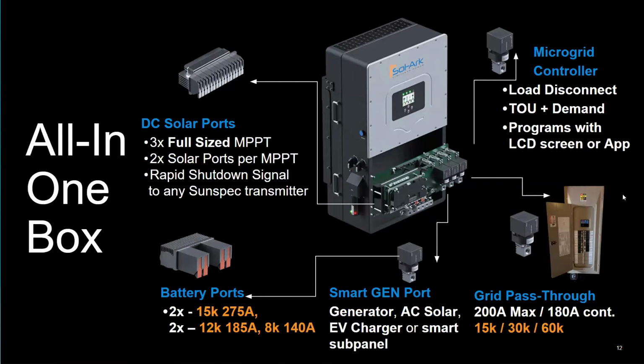Now, beyond that, there are a couple of strategies you can utilize. Instead of doing a 200 amp breaker, you could do a manual bypass, although you would still have to figure out overcurrent protection of that bypass. There are low budget ways you can do it too. You can double lug off the grid side of the system and put in a 40 amp generator interlock kit, which most service panel companies now make pre-configured sub panels for. That would give you temporary service power if you needed to take the system offline for servicing, without the cost of a bypass switch.